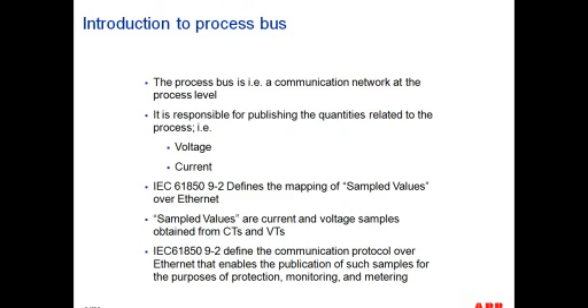So the process bus is in essence a communications network at the process level, and we'll see some pictures in the next few slides to really illustrate that. In essence, this communications network is responsible for publishing quantities related to the process. In the case of electrical substations, we're really talking about voltages and currents. IEC 61850-9-2, which is the part named 9-2, defines the mapping of sampled values over Ethernet. So if you were to get a copy of IEC 61850-9-2, all it essentially defines is the protocol mapping: how we're going to publish these samples and what type of addressing scheme is necessary to publish them over an Ethernet frame.